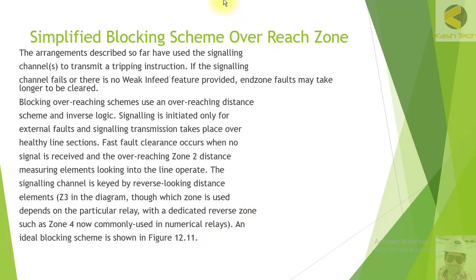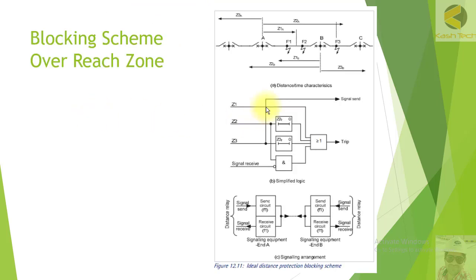The blocking scheme involves two substations, A and B. If a fault occurs at F1, the relay at station A will trip in zone 1 and the relay at station B will also trip in zone 1, so the fault will be cleared immediately. But if the fault is beyond zone 1A — at F2 — the relay at station A will see the fault in zone 2 in the forward direction.